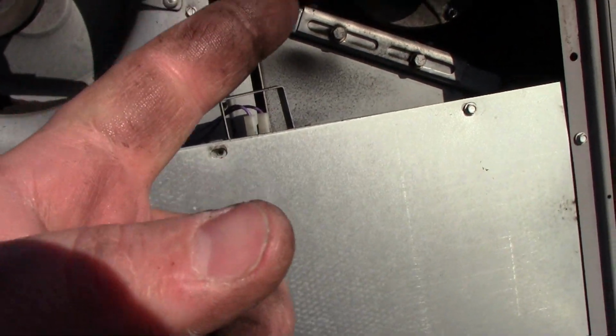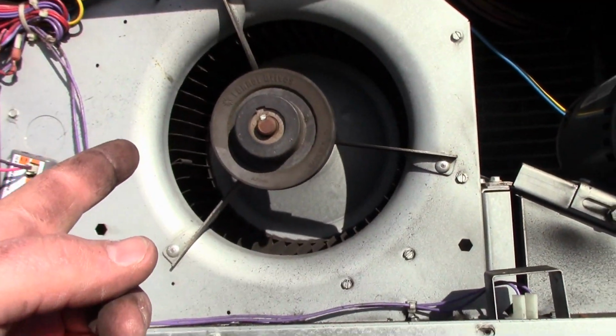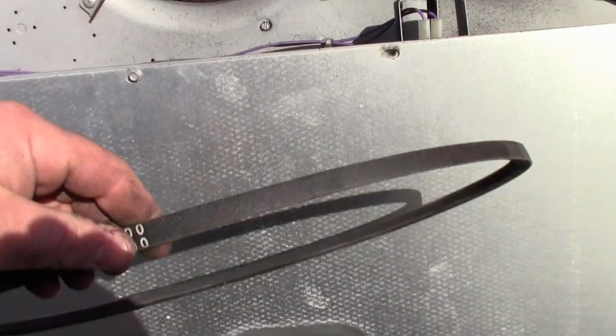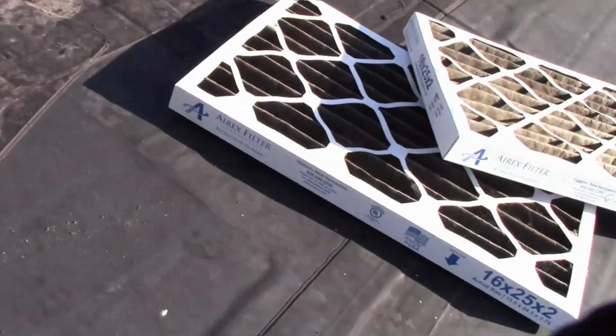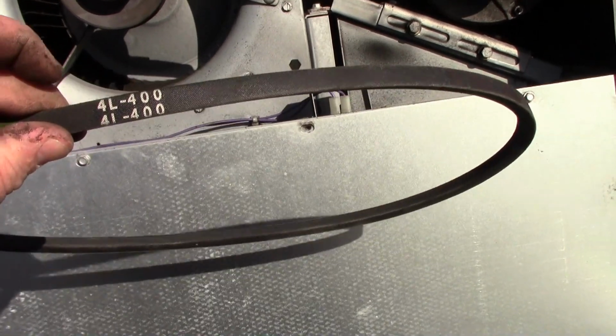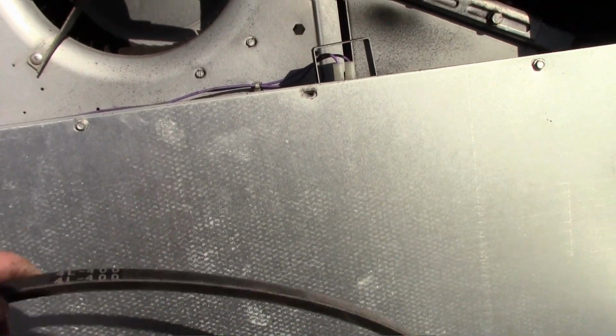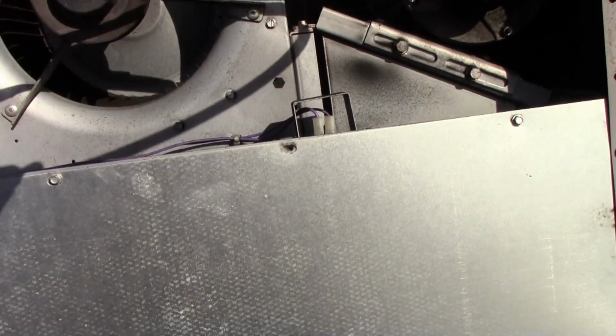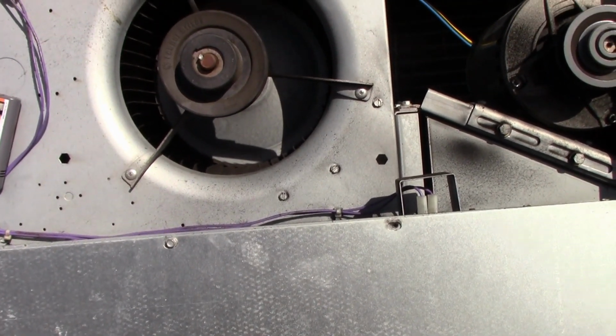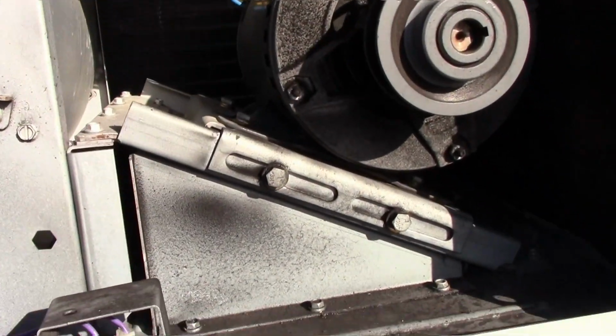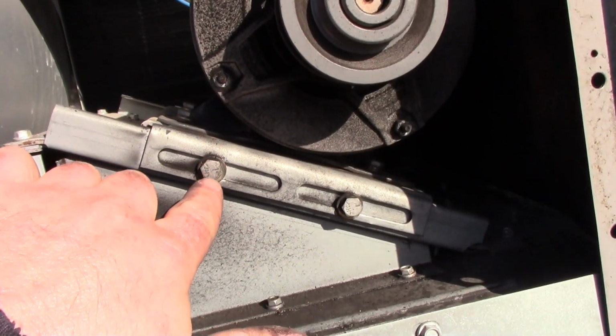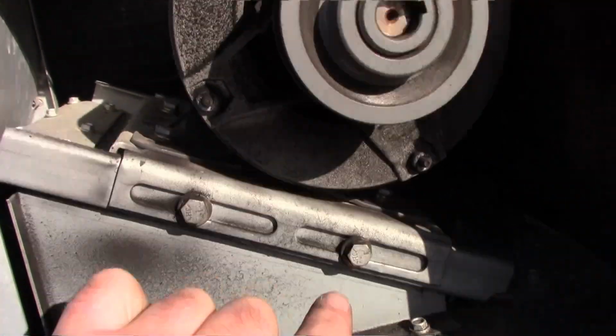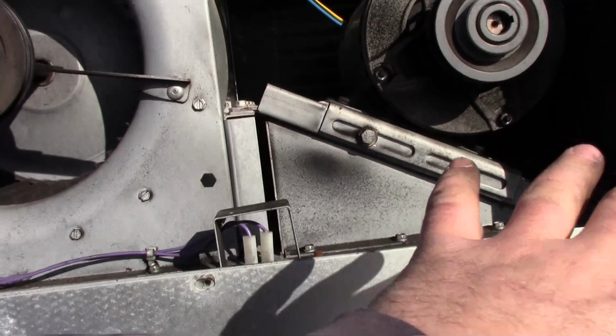This is only half a horse motor here, turning this little rinky-dink blower. Yeah, it's not going to last as long, but as long as they keep up with their PMs, which I'm going to recommend they do, you're perfectly fine with this. So I'm going to put this on, and then we're going to start it up, and we can measure our amperage. If you do have to adjust this belt, there's a screw here, and there's one all the way in the back there, and that whole plate slides up and down.